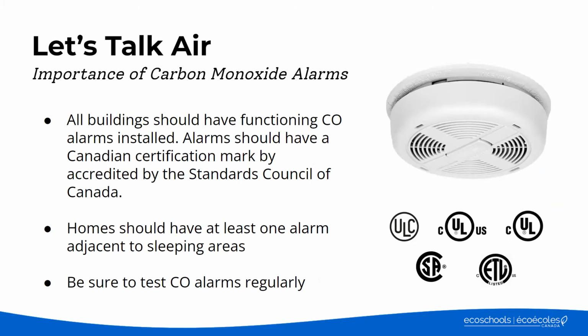Ensure that when purchasing a smoke or CO alarm, there is a recognized Canadian certification mark from an organization that is accredited by the Standards Council of Canada. These marks, such as CSA, CUL, ULC, or CETL, should appear directly on the product, not just on the packaging.